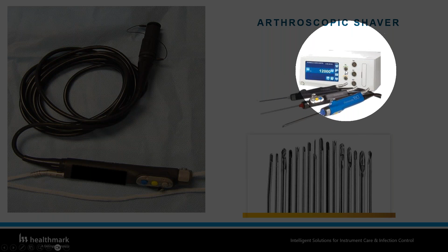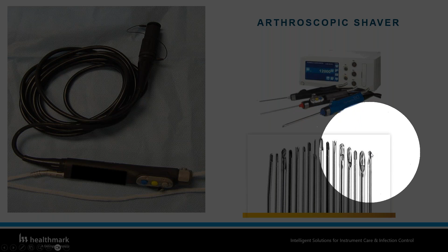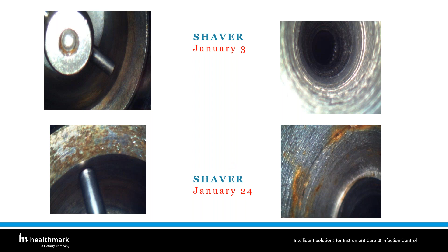So we talked about the arthroscopic shaver, used in minimally invasive procedures. This is the shaver that was used on that patient, similar model and number. For those who are not familiar, the shaver, which is a high-speed drill, gets attached to the machine that powers this high-speed drill. Then the surgeons select various high-speed razors that actually go into the joint and remove the debris inside the joint. Looking at one of those shavers on the inside, we received a brand new one on January 3rd, and this is what it looked like new. After processing over 3 weeks, we see some rust and some other debris inside. And these were obviously processed following the manufacturer's IFU.